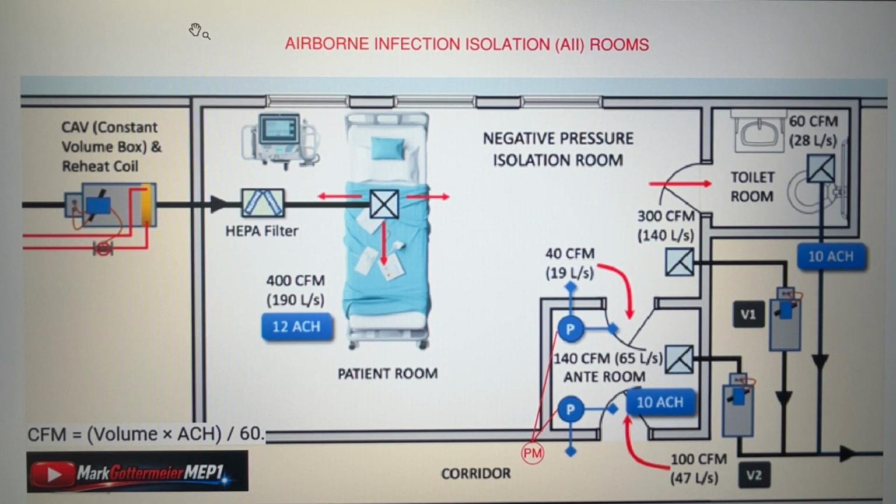So the airflow supplied to this room has to be balanced with the exhaust airflow to create a negative differential pressure with respect to the adjacent space. The exhaust from these rooms is not recirculated into the HVAC system. Instead, it exhausts direct to outside air where the atmosphere can provide sufficient dilution to make the resulting air safe.